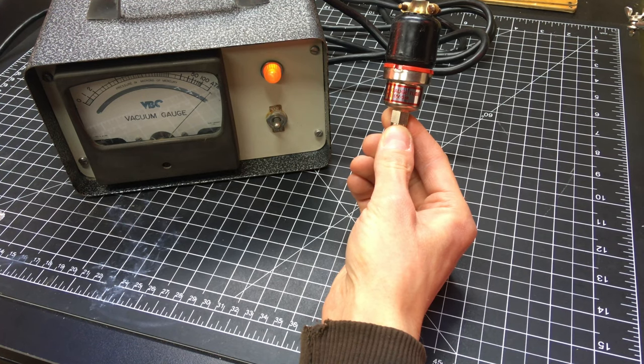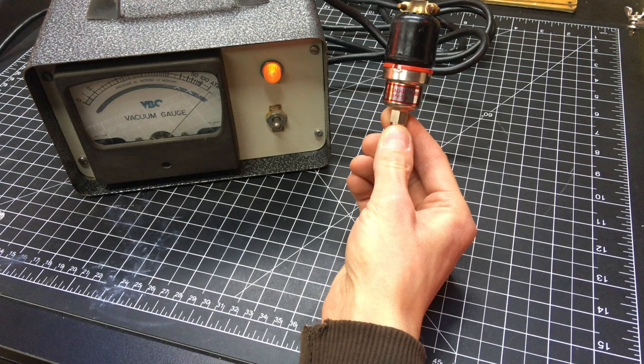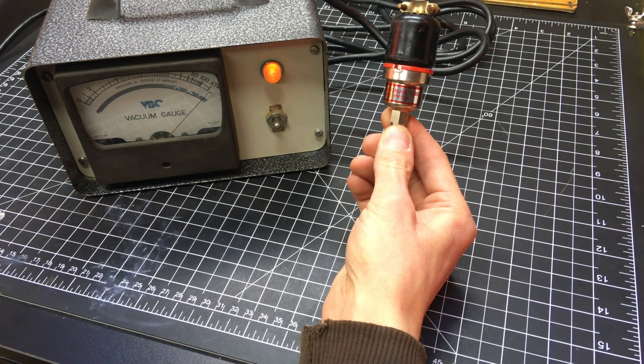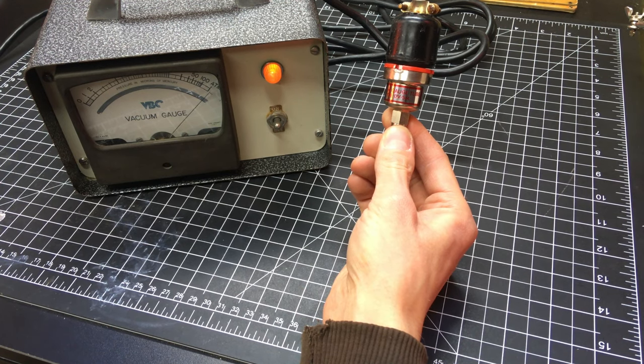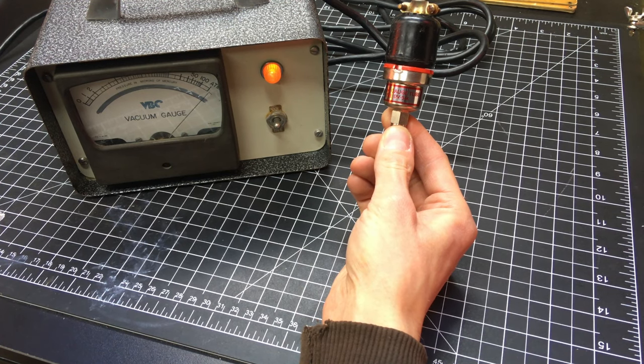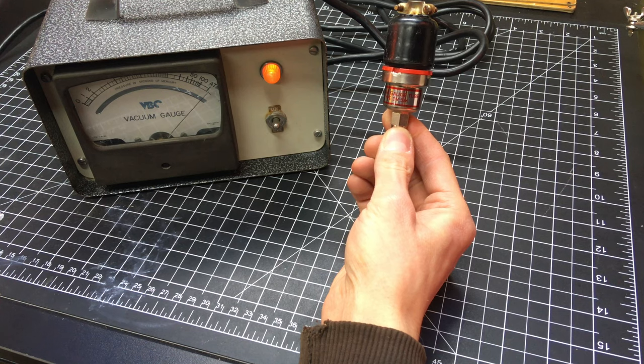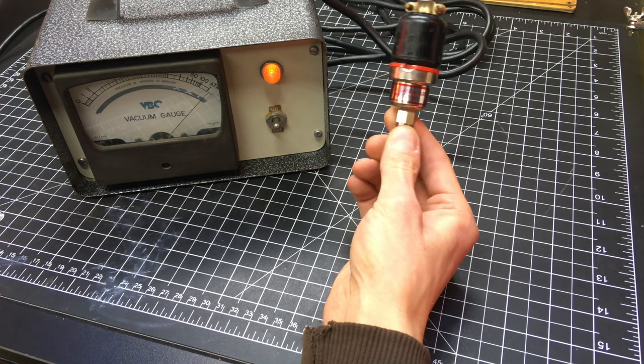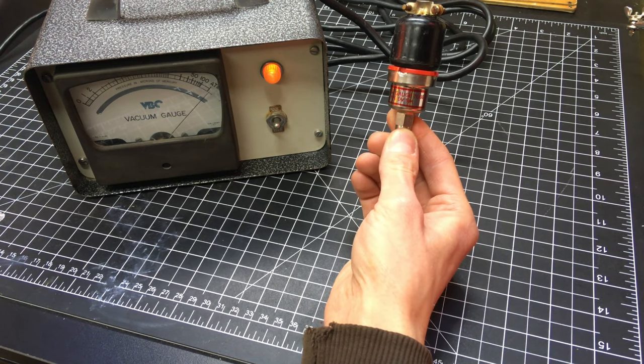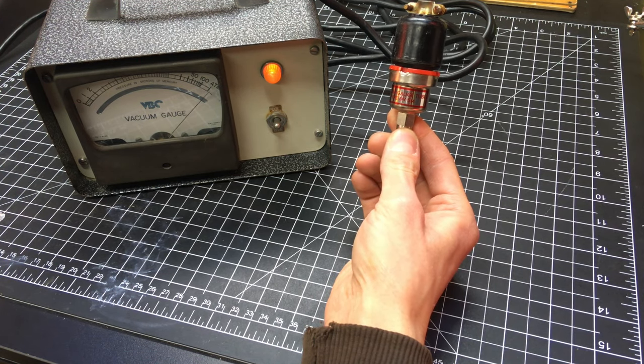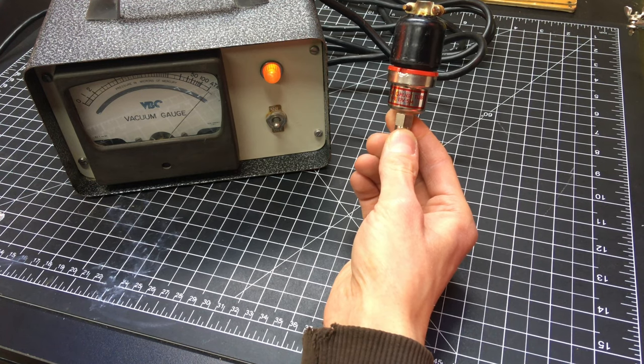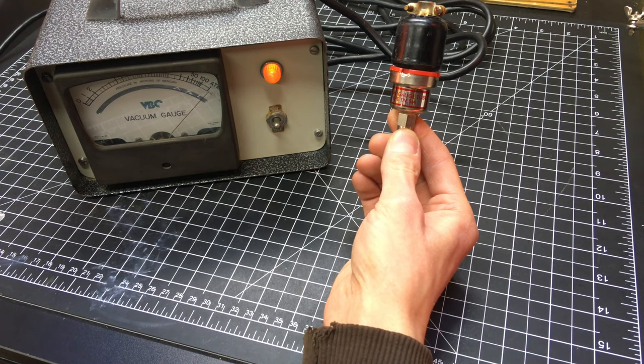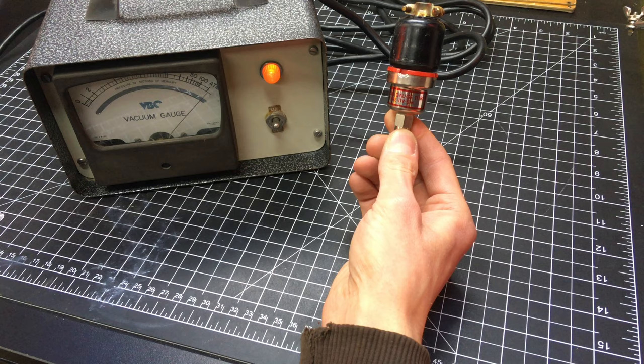It starts moving a little bit. Now it's not going to move a whole lot because it's just going to the ATM. We're just at atmospheric pressure right now because this gauge tube is not under vacuum at all. So right now the needle's pointing right to ATM which is where it should be.